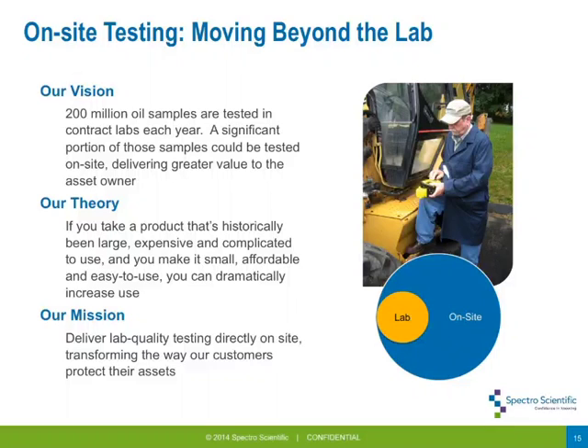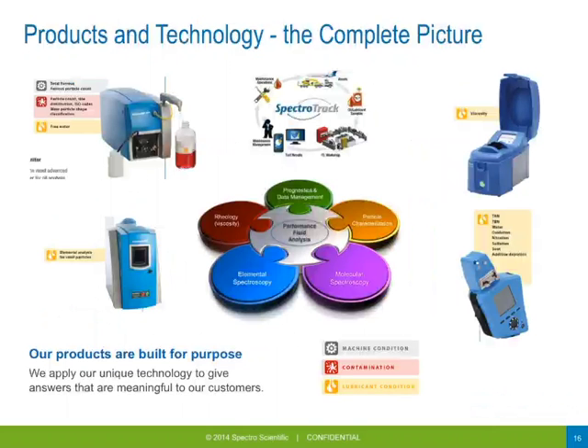That's our mission — to deliver that type of technology. We have developed a series of technology tools that are both portable and benchtop, which collectively you can mix and match to come up with a complete picture for lubricant condition monitoring, contamination condition monitoring, and machine condition monitoring. The key takeaway is that if you start with contamination control as your starting point, some of the initial portable technologies will have great appeal. For engine owners, portable tools such as the FluidScan, a fuel dilution meter, or a viscometer allow you to detect problems very quickly.